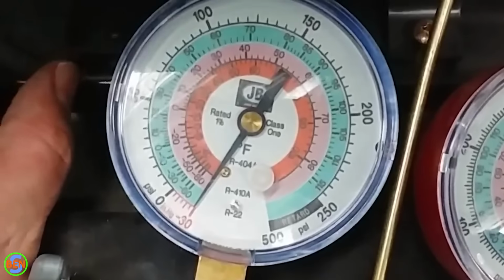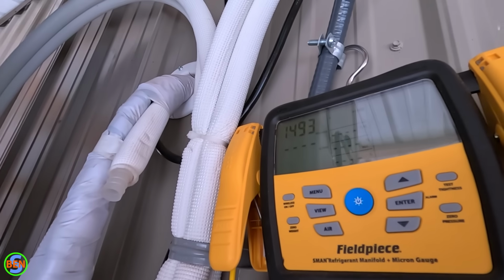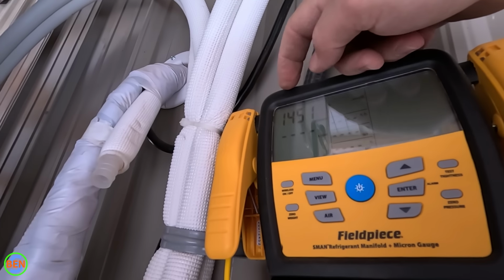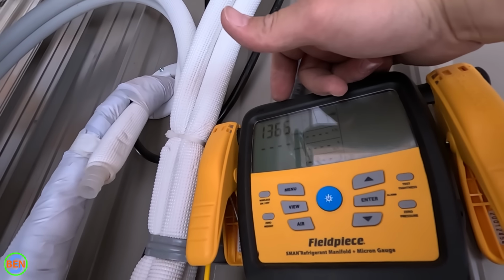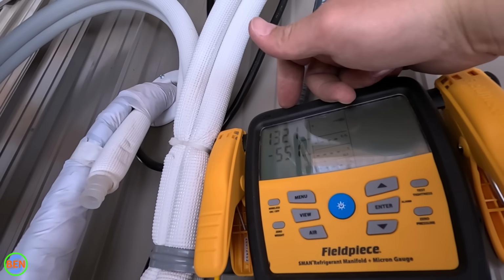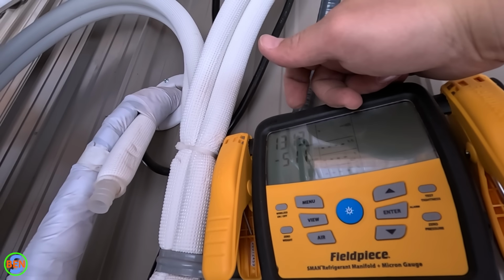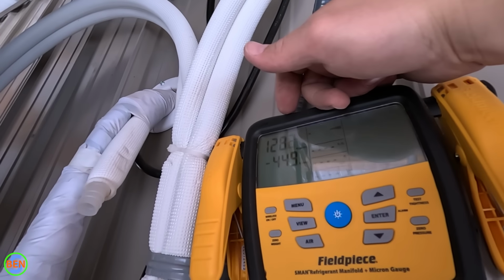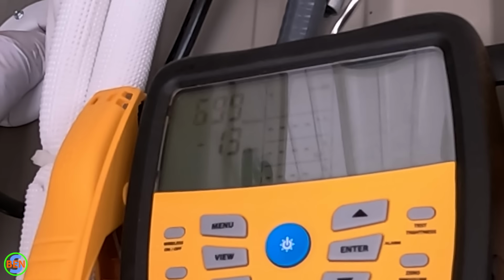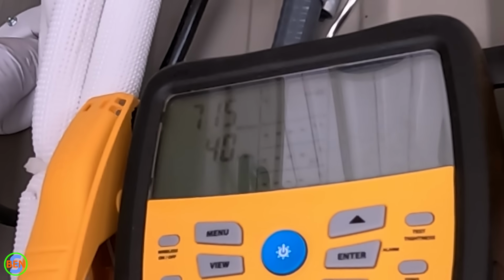And generally speaking, just for your knowledge, on a digital gauge, once you're looking at the microns, you usually can't pull a vacuum below 2,000 microns if you have an actual physical leak where air is coming into the unit. You'll just never even get below 2,000 microns. If you're able to get it down under 1,000 microns, but then it climbs back up into the mid thousands, you probably have a little bit of moisture in the system, and you're going to want to pull that vacuum again and possibly put some dry nitrogen back into the system and then pull vacuum again.